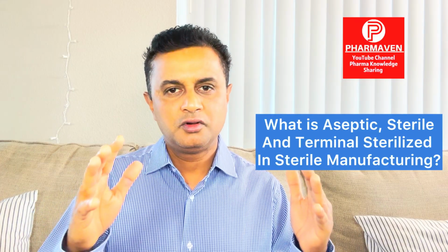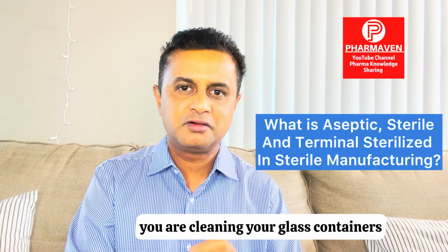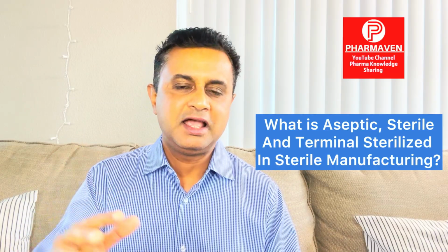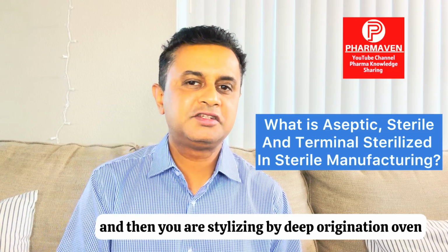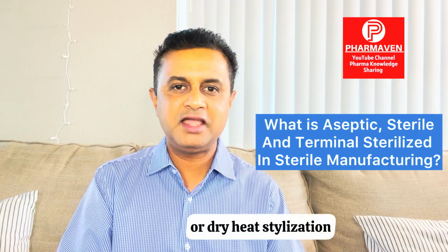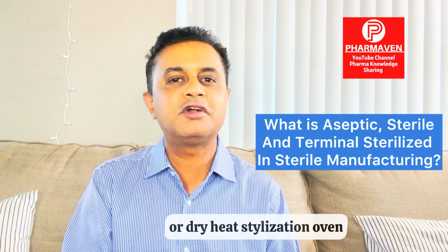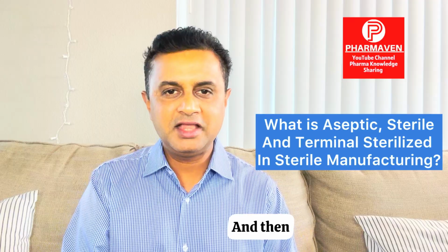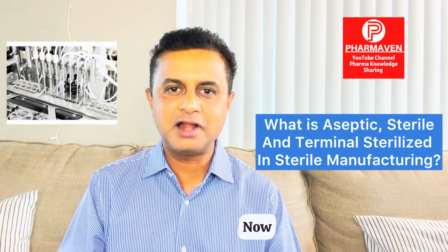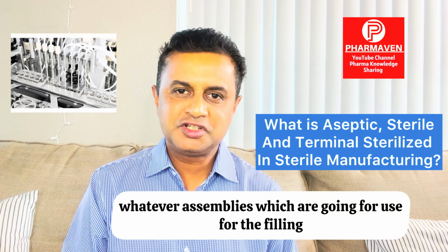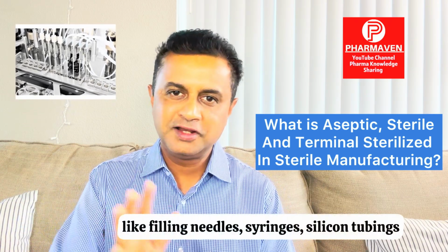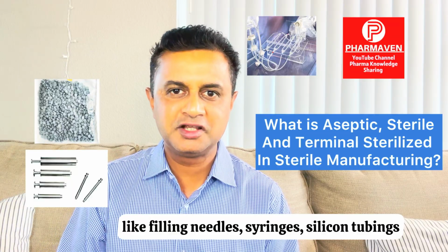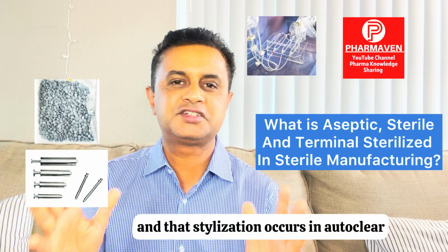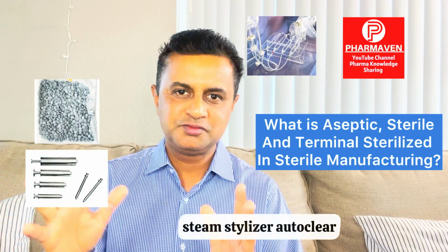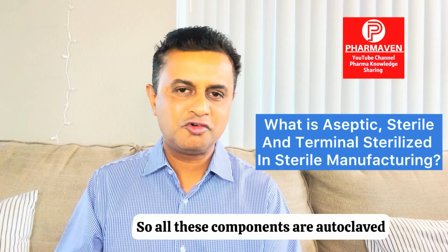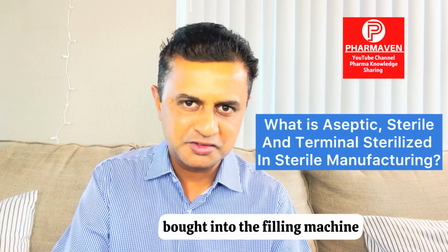So you clean your glass containers, vials or ampules, and then sterilize by depyrogenation oven or dry heat sterilization tunnel, and then it comes to the filling machine. Now whatever assemblies are used for filling, like filling needles, syringes, silicone tubings, everything has to be sterilized, and that sterilization occurs in an autoclave, a steam sterilizer autoclave. So all these components are autoclaved and brought into the filling machine.